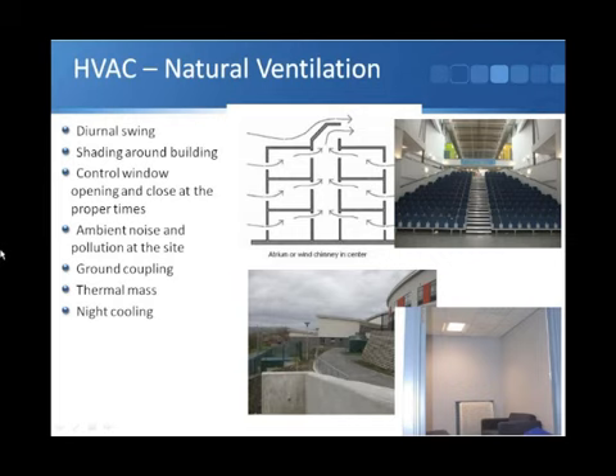Ground coupling is important, so things like ground tubes that will allow us to bring the air in through pipes in the ground or through natural ground spaces will allow us to pre-cool the air in summer and preheat it in winter. And thermal mass is important as well. So the building itself is able to act as a thermal store. In the winter, it absorbs heat, keeps itself warm overnight. The building is still warm the following day. And in summer, will allow itself to cool down all night. So that night cooling enables the building to operate during the day satisfactorily.